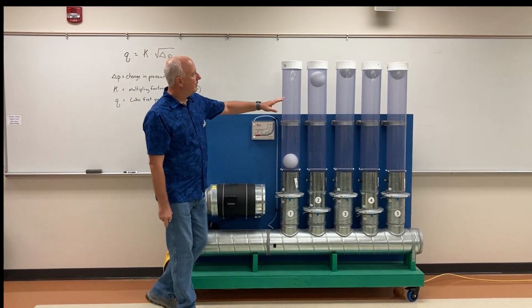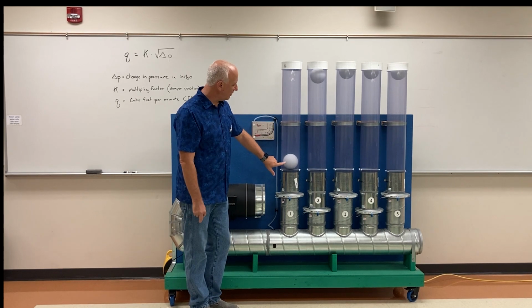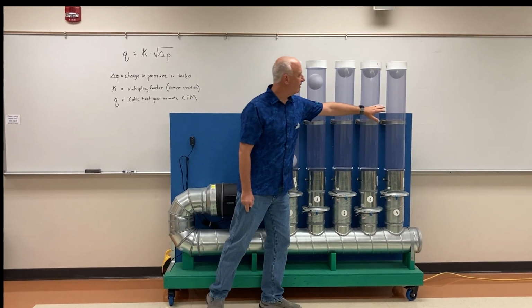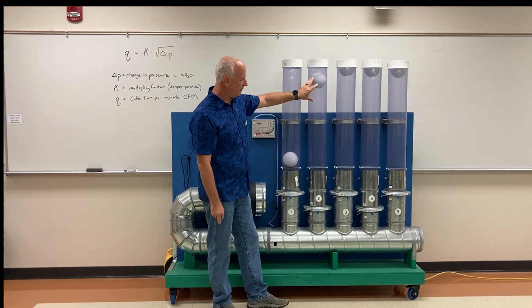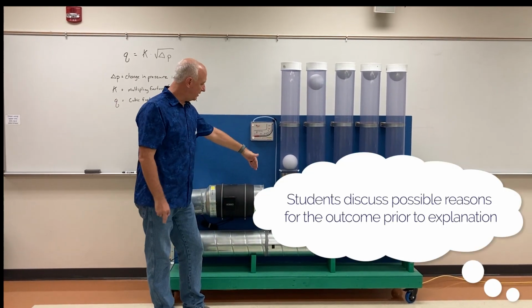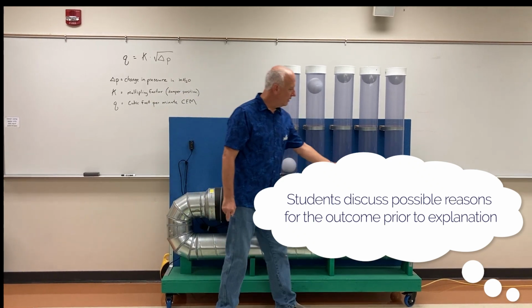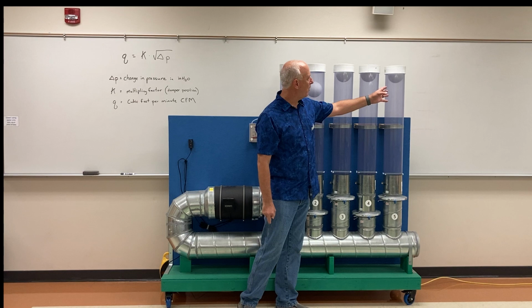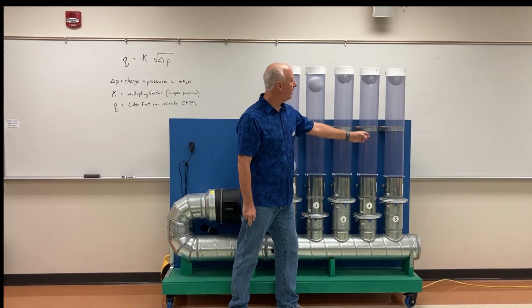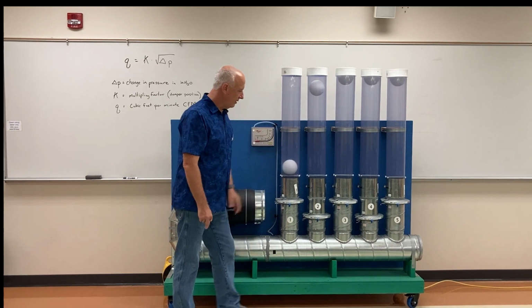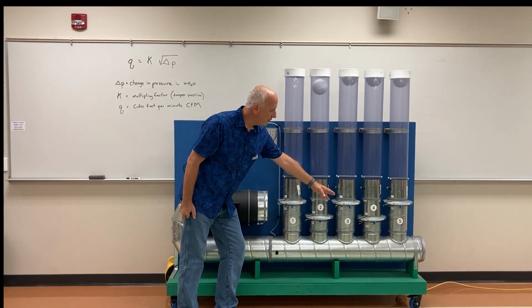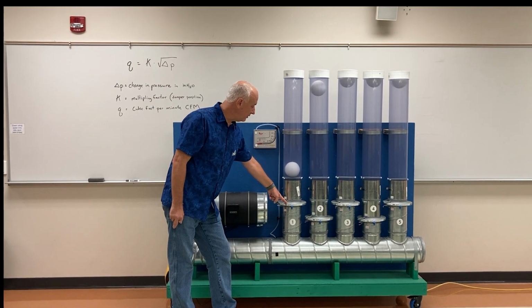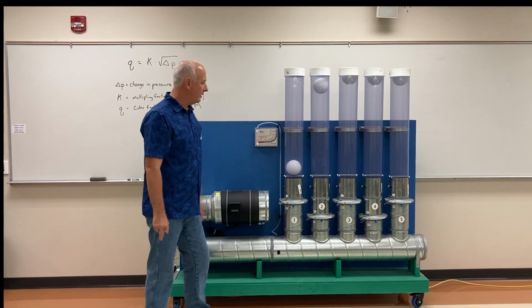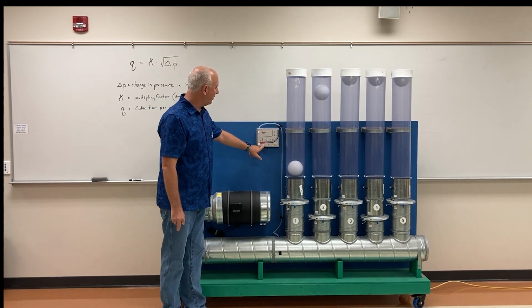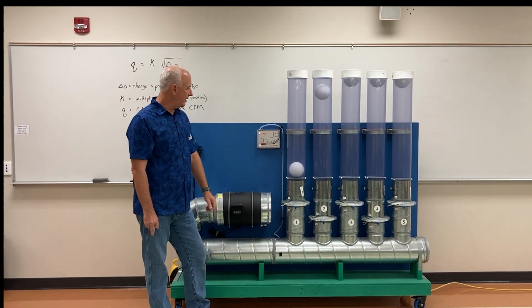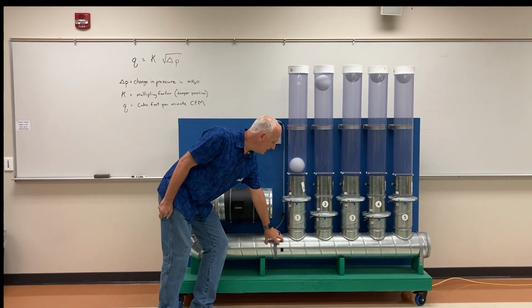As you can see, this one's getting a little bit of air, just a little bit of movement. These three are getting most of the air, and this one's not far behind. But what happens is when the fan comes on and goes across, the pressure builds up and pushes this ball up, then the pressure builds up this way and pushes this ball up and all the way across. At first, the air is just going by here so fast that it can't turn and get into this tube, and it's just going to the end. The manometer is reading 0.05 inches of water, so that's the pressure inside the ductwork.